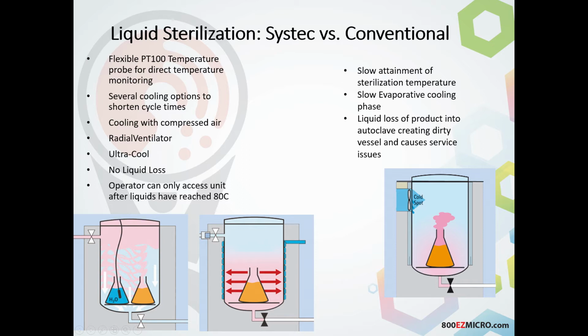And at this point, you can't program it to be any less than 80 or any more than 80 degrees. So that way, not only are we maintaining correct sterilization of our liquids, we're also making sure that we're going to keep all of our operators safe as well. So in conventional systems, again, it's slow attainment of the sterilization temperature. The only cooling is evaporative cooling. So what it will do at that point is it's going to boil over and evaporate, and you're going to have heavy liquid loss, and you're also going to create a very dirty vessel, which will cause service issues, as we mentioned before. So that is our process for liquid sterilization.